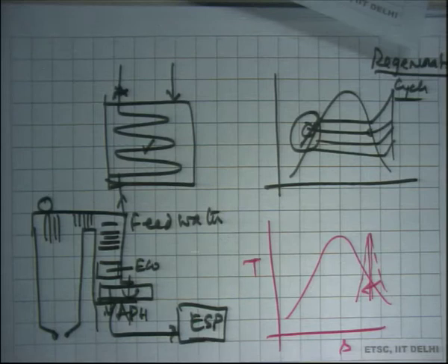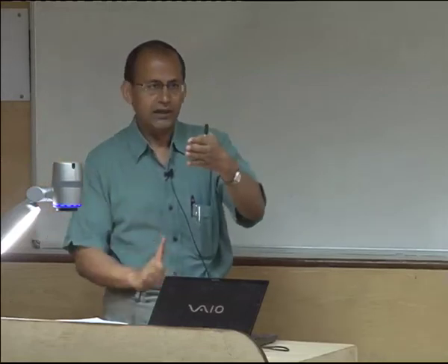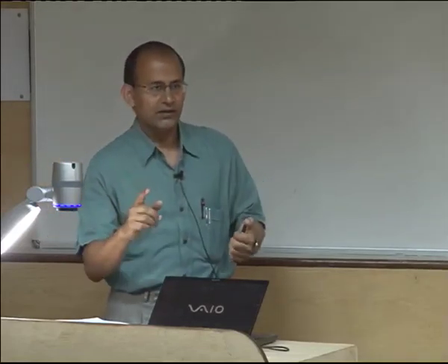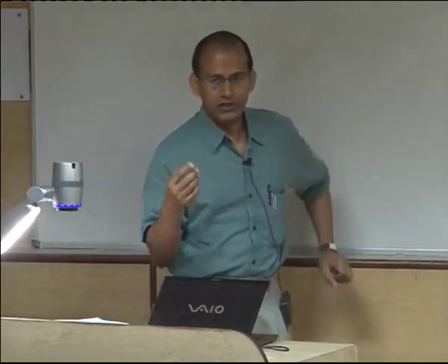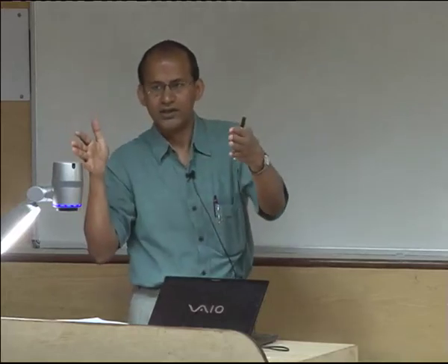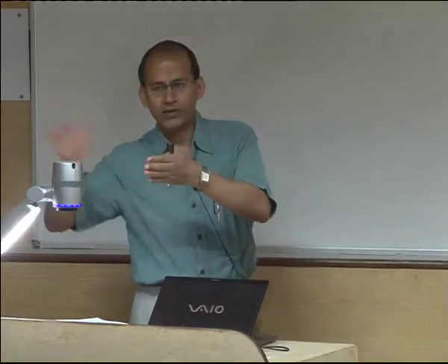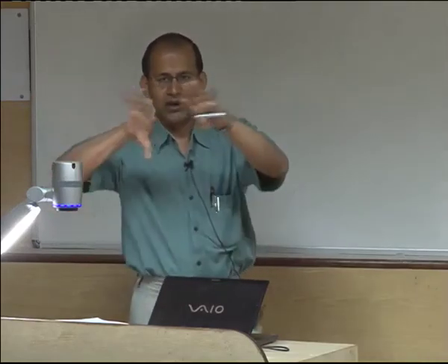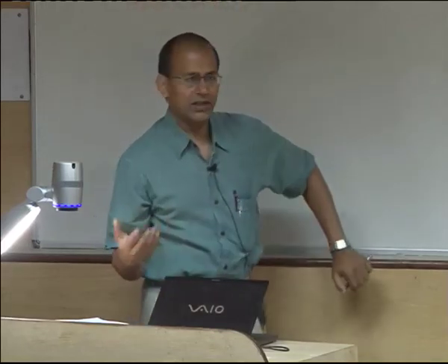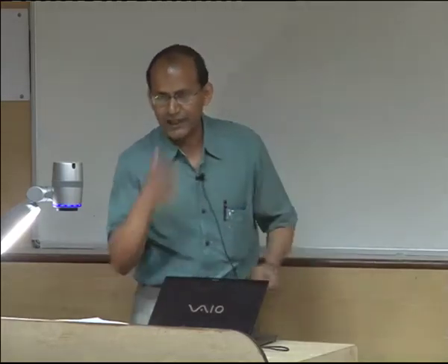Okay, where using a high DC voltage, you are going to remove the ash from the air stream, because you have parallel plates which are grounded, and there are wires in between which give high voltage DC. Okay, the corona discharge from these wires charges the particles around, and the charged particles migrate towards the ground. Okay. So, from time to time you have hammers that rap the plates, the electrodes. So, whatever ash that is stuck to it falls down by gravity, and you collect it in the hopper at the bottom. Okay.